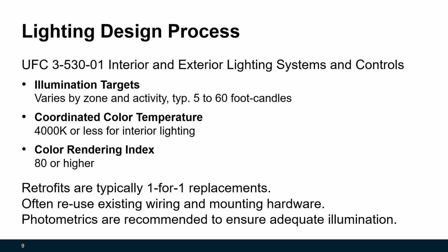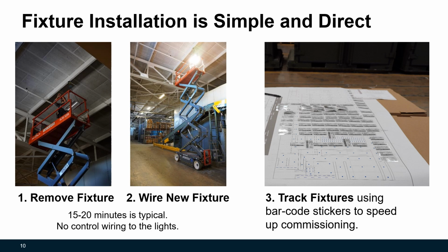We selected the lighting hardware to meet the UFC lighting specifications, including the illumination targets, color temperature, and color rendering index. Typically, the lighting installation was a 1-for-1 replacement of the existing fixtures. In some cases, we removed lights, and others, we added some lights, but mostly it was a 1-for-1 replacement. As you'll soon see, sometimes the baseline lights really aren't bright enough. The fixture installation was straightforward and direct. Typically, this just involves removing the old fixture, replacing it and rewiring the new fixture, and tracking the serial numbers. That last step is not required, but it speeds up the commissioning process. The lights come with stickers that you can use to track on a facility printout map, and the electricians had no problem doing this during the installation.